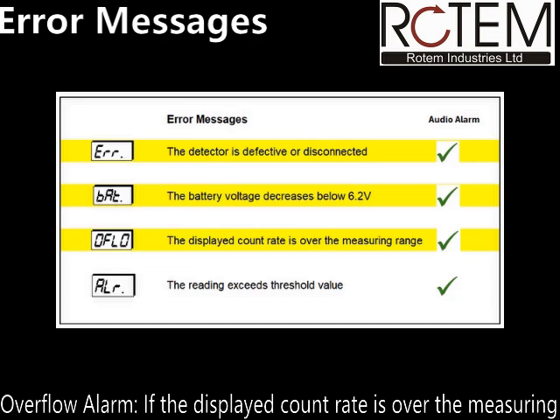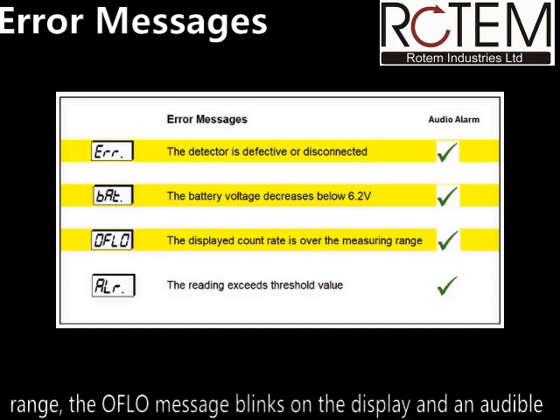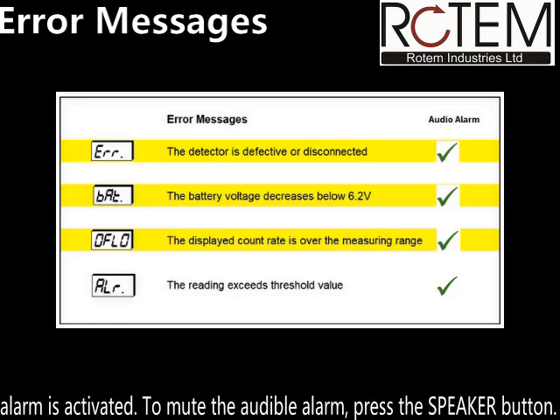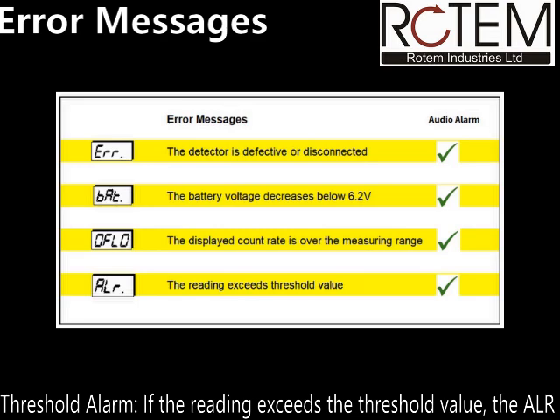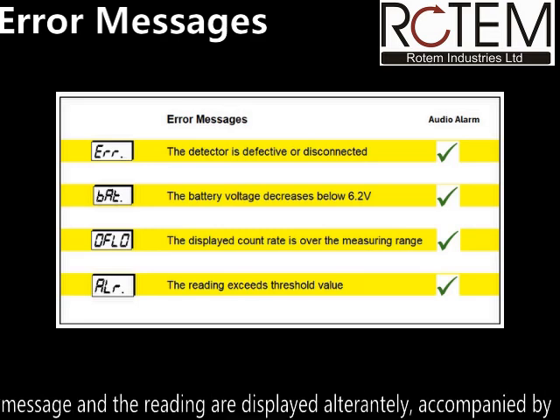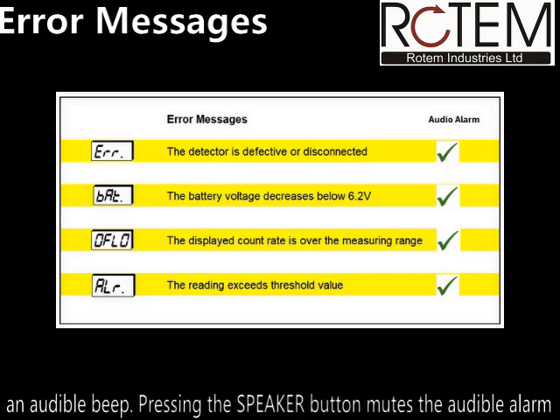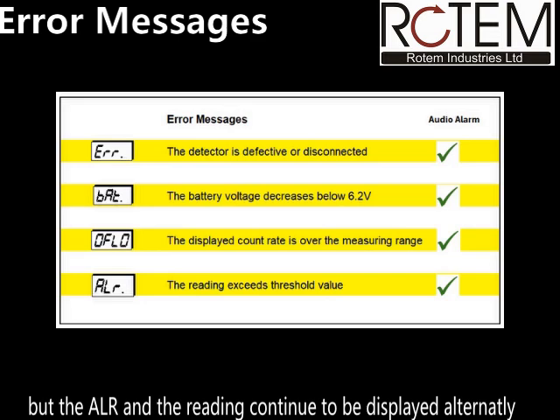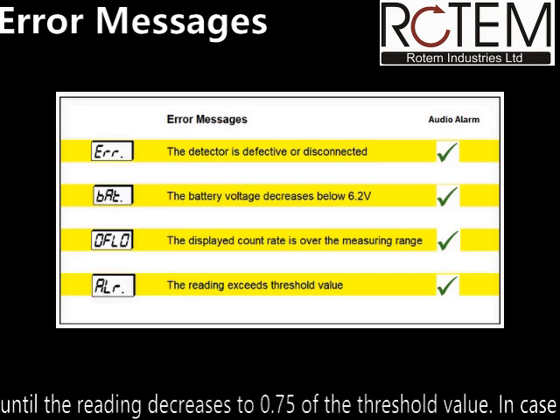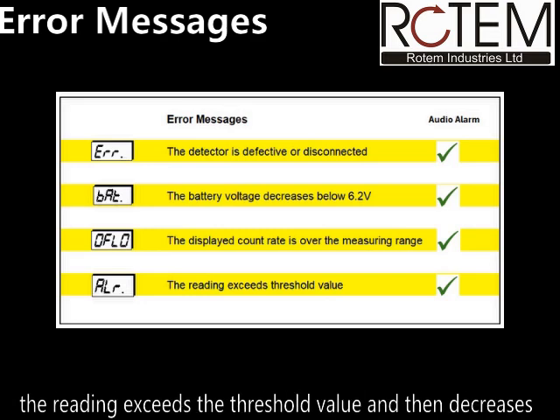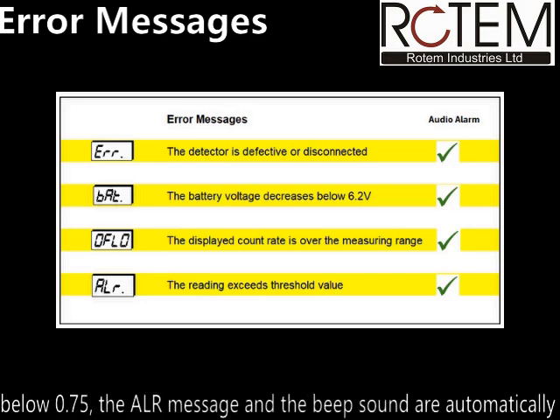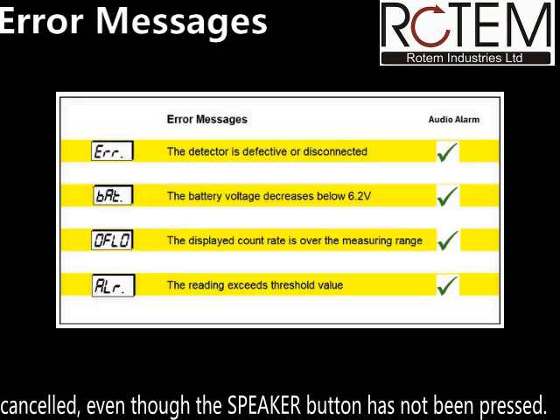Overflow alarm. If the displayed count rate is over the measuring range, the OFLO message blinks on the display, and an audible alarm is activated. To mute the audible alarm, press the speaker button. Threshold alarm. If the reading exceeds threshold value, the ALR message and the reading are displayed alternately, accompanied by an audible beep. Pressing the speaker button mutes the audible alarm, but the ALR and the reading continue to be displayed alternately, until the reading decreases to 0.75 of the threshold value. In case the reading exceeds threshold value and then decreases below 0.75, the ALR message and the beep sound are automatically cancelled, even though the speaker button has not been pressed.